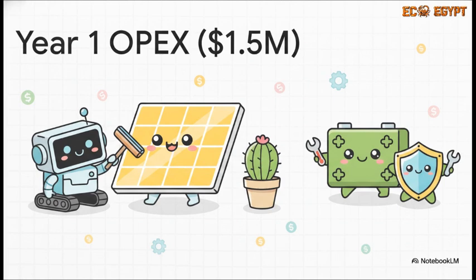Flipping over to the operational side, the OpEx, some fascinating real-world details emerge. The total for year 1 is $1.5 million. We have to budget $180,000 just for robotic module cleaning, running 12 times a year, simply because this plant operates in a harsh desert environment. You've also got significant all-risk insurance and dedicated BESS maintenance for things like cooling fluids and BMS calibration—because engineering isn't just about building the thing, it's about keeping it running efficiently for decades.